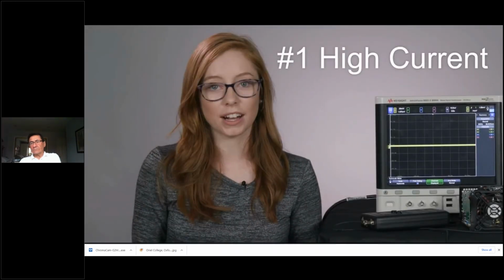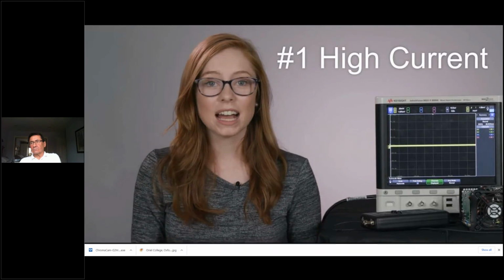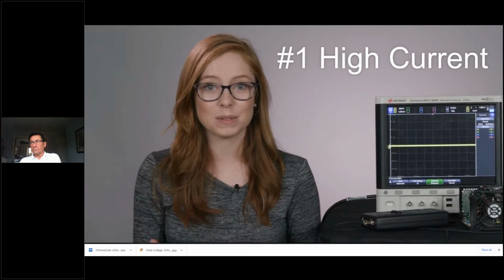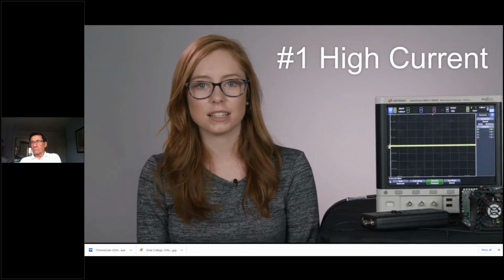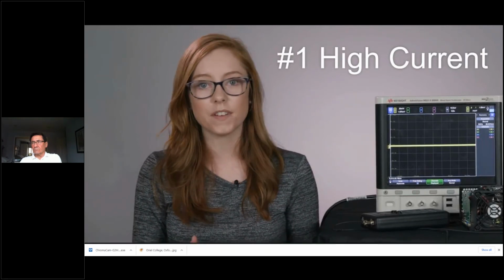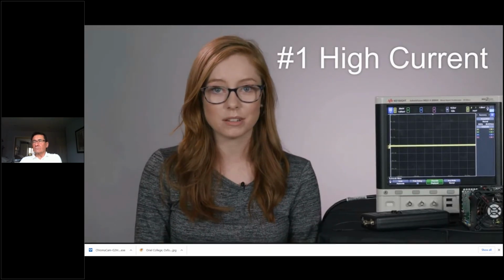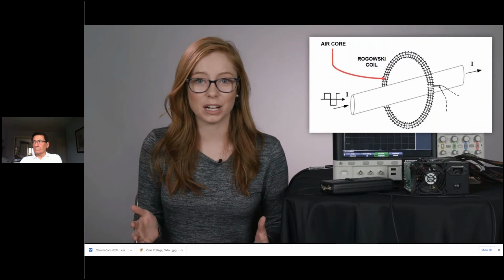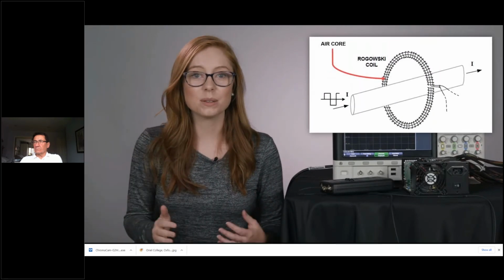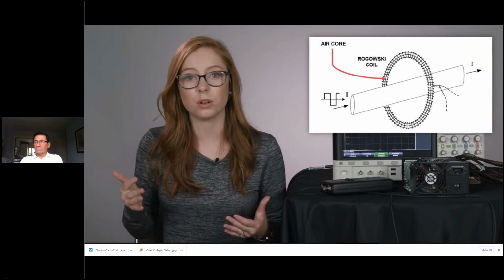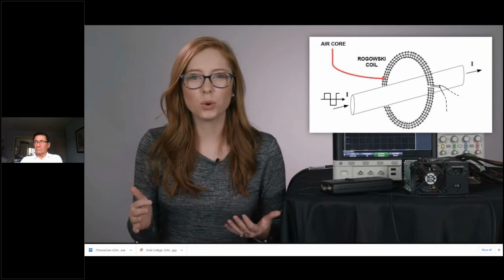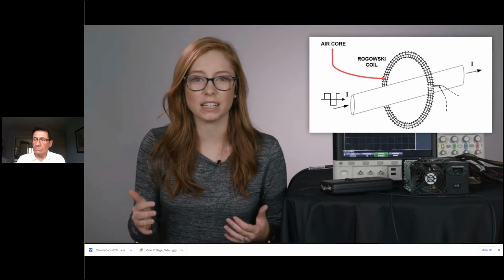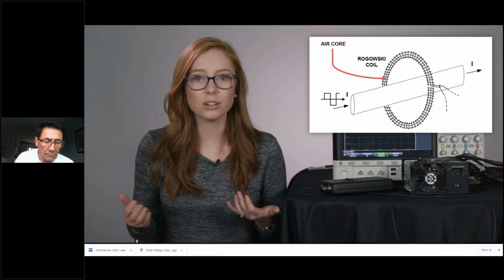Let's start with how to measure high current. And when I say high current, I mean high current, as in hundreds or thousands of amps. You'll often run into large currents like this when measuring the startup of a device or the switching of a switch mode power supply. A Rogowski coil current probe can measure high currents because it uses an air core instead of a traditional metal core. With a metal core, we'd have to worry about too high a current saturating it, but with air, we don't have to worry about that.